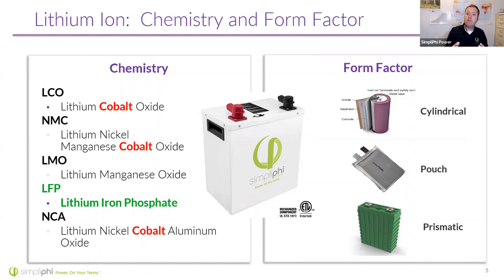When you look in one of our batteries, you'll see cylindrical cells, the top one here. Cylindrical cells have a metal case around them, which is able to contain thermal runaway events very well. It does have a vent at the top, which controls that release of gases. They're not pouch, they're not prismatic. Pouch cells, which are the cheapest of all the form factors to construct, tend to be prone to puncture, and they can swell and contract.